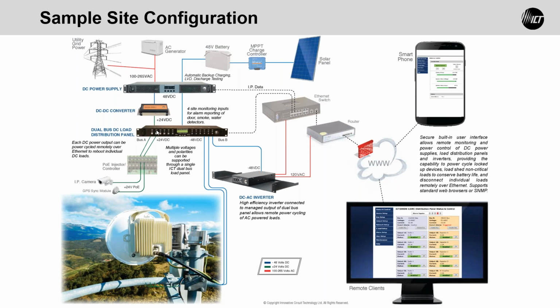So these six outputs are 24 volts that could be powering a PoE injector or a PoE controller, IP cameras, a GPS module, any of these devices running off 24 volts. And then you've got direct neg 48 powering these higher power radios. And let's say you've got some AC product, either a router or Ethernet switch running off AC. So we'd take that neg 48, go into our inverter, and it would convert that neg 48 into 120 volts AC to power these two devices.